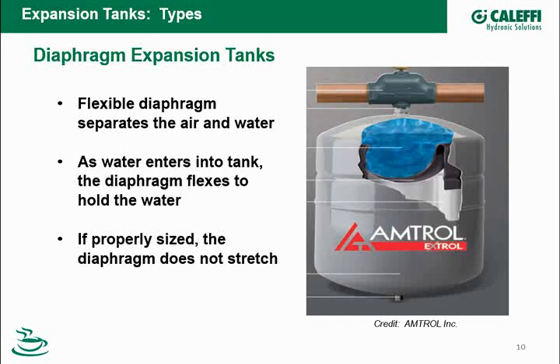Now, design-wise, with a diaphragm tank, a lot of times the question comes up: should I be concerned with that diaphragm stretching? If the tank is properly sized for the application, the diaphragm simply inverts, and then when the system cools down, it returns to its original shape to push the expanded water back into the system, but there's no stretching, so the stretching really doesn't play into the life cycle of the diaphragm expansion tank.